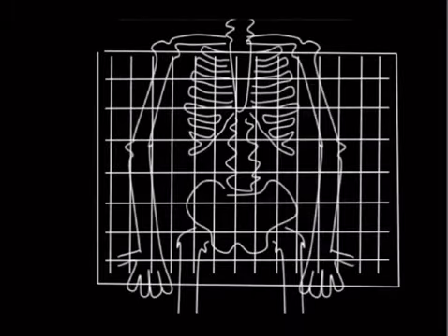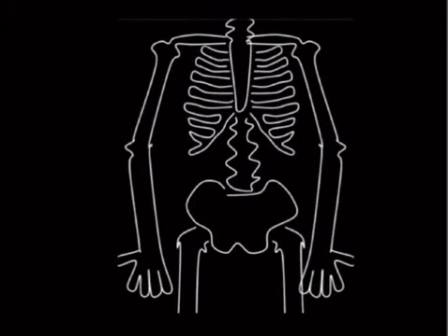During the exposure, which is prolonged when you're using a grid, X-rays still have to come in a straight line as the grid is moving up and down, but it'll overlap in those portions, so you shouldn't see the grid lines. If you do see the grid lines, that means the grid has failed, so you should not see them.